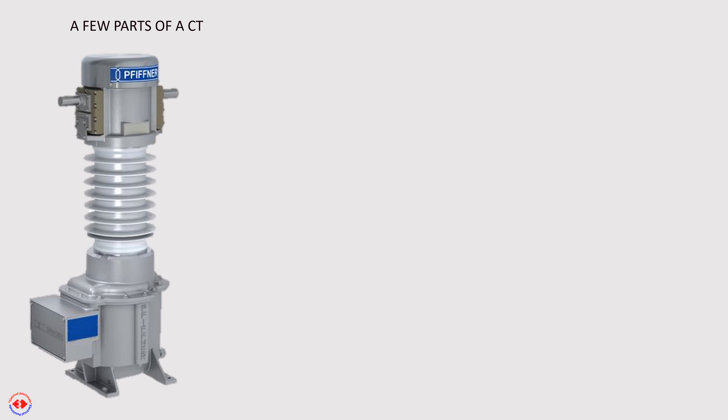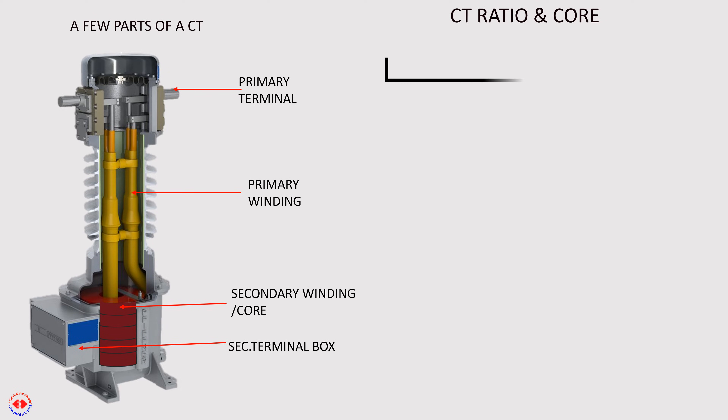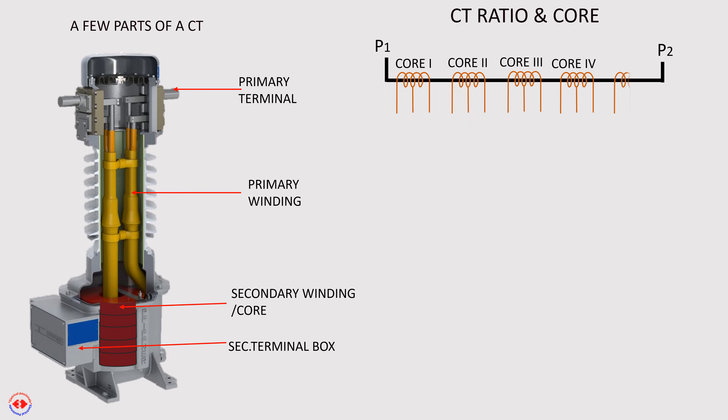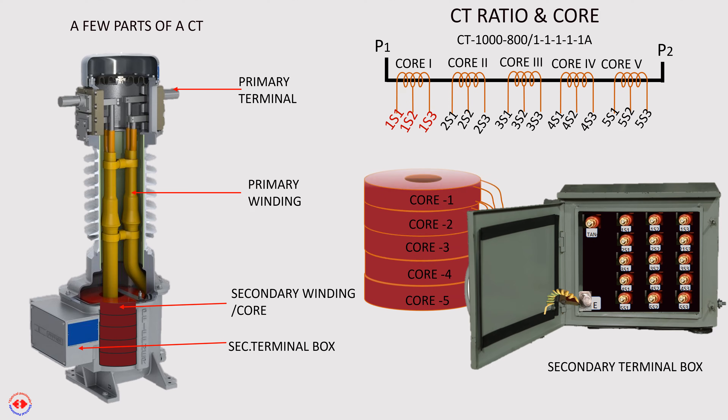This is an image of a high voltage outdoor current transformer and its various parts. The CT has 5 secondary cores or windings of ratio 1000-800/1-1-1-1-1 ampere. This is a picture of a 5-core CT secondary terminal box. When CT primary is required to deliver 1000 ampere, connection of CT secondary will be between 1S1 and 1S3. 1S1 and 1S2 are for the first core, and the same procedure will be followed for the other cores.